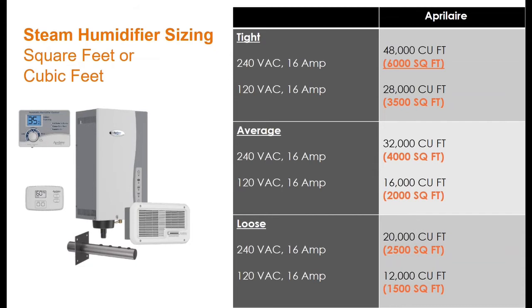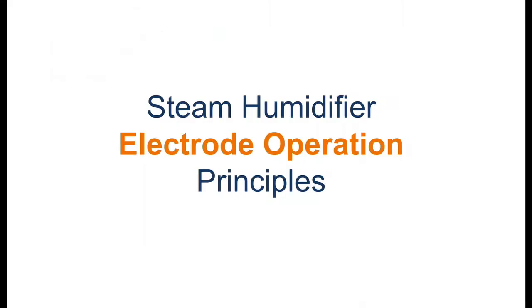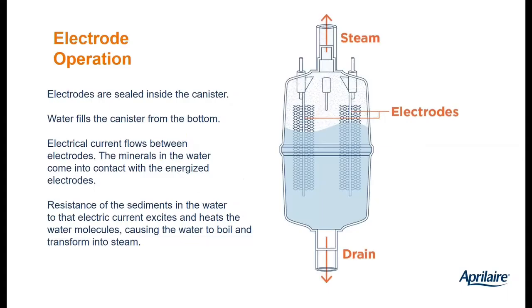At maximum voltage and amperage — 240 volts, 16 amps — we're going to produce 34.6 gallons per day. That is a lot of humidity, and that's where I think it's worthwhile to get this supplied with 240. But if you've done the calculations and don't need that much humidity, a lower voltage would be fine. Just be aware that at 120 volts even at 16 amps you're down to 16 gallons per day. Think of it this way: a tight house at 240V 16A can humidify 48,000 cubic feet — a 6,000 sq ft house with 8-foot ceilings. Drop to 120V 16A and you're only humidifying 28,000 cubic feet.